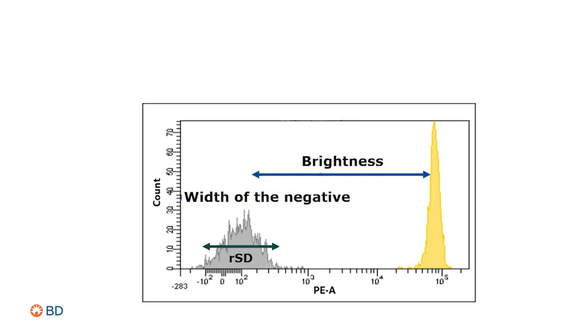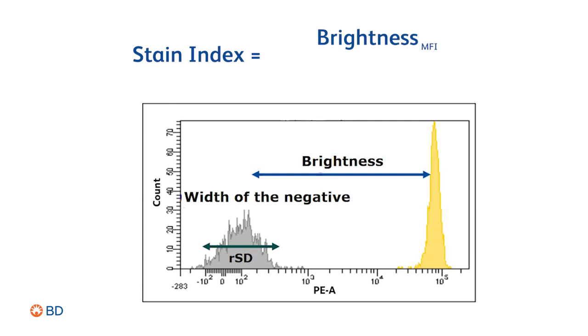The standard metric for measuring fluorochrome resolution is the stain index, which is the difference in fluorescence intensity of the positive and negative populations divided by two times the robust standard deviation of the negative population.